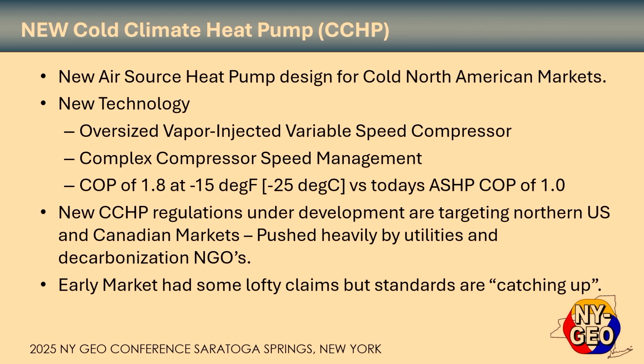That heavy lifting is typically compression ratios over 4. If you want to look at it simply, you could just look at the head pressure to suction pressure, and if that ratio is over 4, then you can benefit from vapor injection there. It is a complex compressor speed management, so they're putting in a larger compressor and then limiting the speeds that it will operate based upon the outdoor temperature. So it's a lot more complex than what most of the products on the market today are.